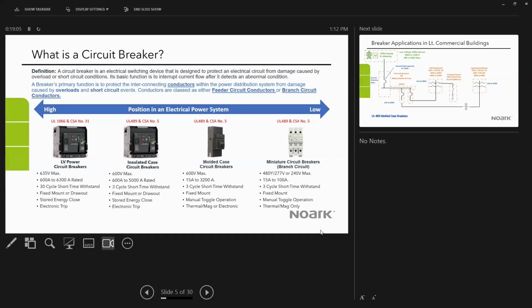So it protects those conductors from overloads caused by loading the circuit with more current than it can stand, or by short circuit events, which are usually much faster and more intense events that happen in a power distribution system. Conductors, based on the electrical codes and standards that we adhere to, are classed as either feeder conductors or branch circuit conductors. And those two terms are important, and we'll talk a little bit more about them later.